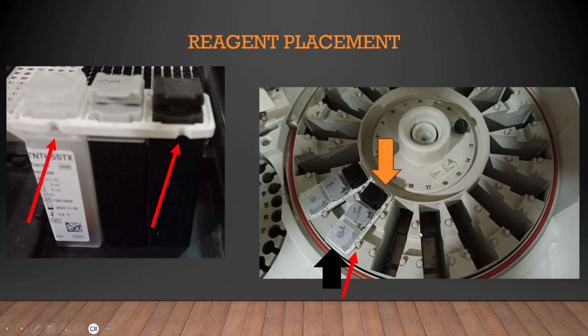Now let us say that for some, like HIV and vitamin B12 and all, instead of 3 there is only one single reagent or 2 reagents. All those things, by thumb rule, will always sit on the outside part, not in the middle, not inside. Like for example HIV or vitamin D, which has multiple extra reagents, apart from the 3 they also have extra 1 or 2. Now those 1 or 2, if it is 1, it will always sit on this end. If it is 2, it will sit on this end, it will never sit on this side. Okay, so this hitch will make sure of that, but unfortunately many technicians will keep it like that, and then they will say, sir, something is wrong. So remember the thumb rule: black is always inside, and if a single reagent or double reagent is there, then they will always be on this side of the circle only.